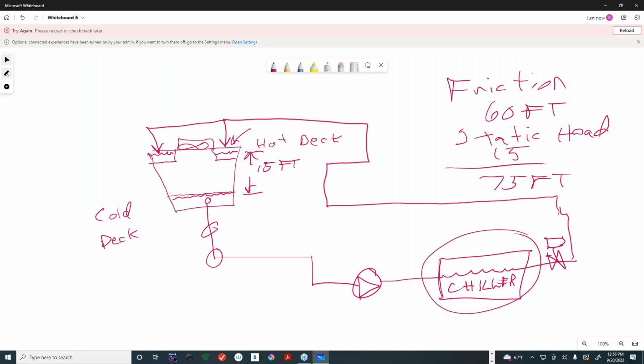Just to reiterate, the pressure loss calculation and the numbers associated with the values and everything you showed earlier in the point-to-point method are all the same, right? That's correct. There's no difference per 100 and all of that, and whatever your limiting values for velocity and maximum unit head loss were, all that remains the same, and then you just have that additional static that you have to take into account.